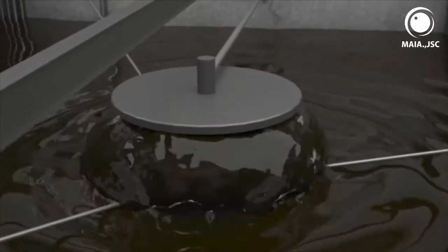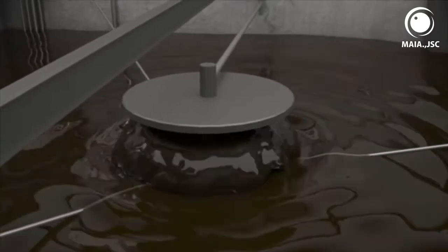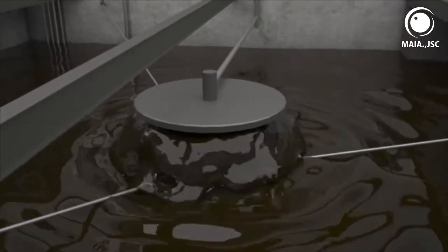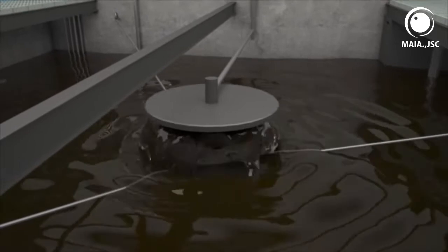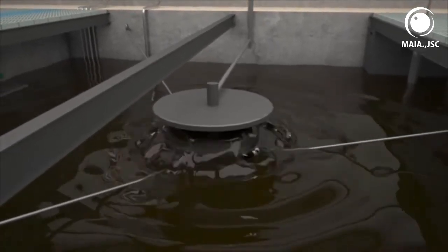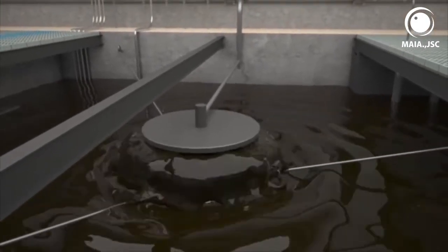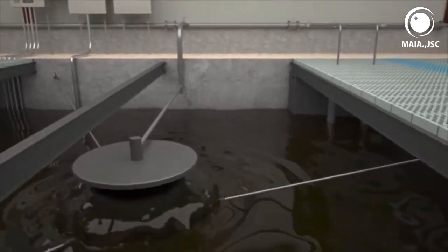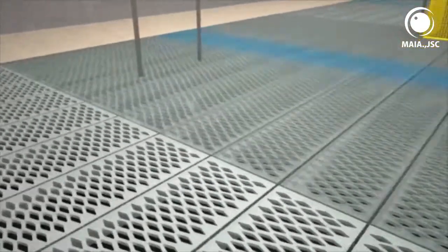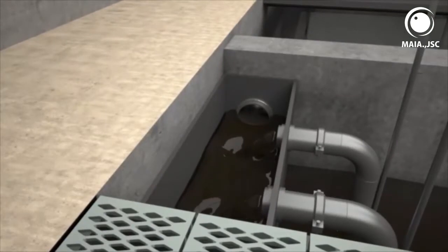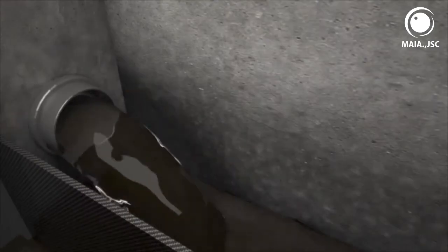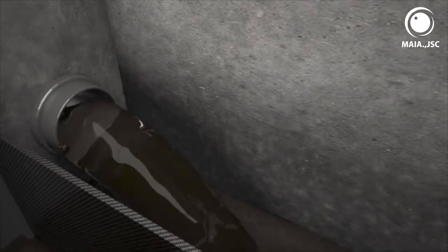This mixing of air and wastewater, along with maintaining the proper room temperature, creates the ideal environment for the aerobic bacteria to digest the biological wastes inside of the wastewater. After approximately 35 hours, the wastewater has been sufficiently treated and is then transferred via airlift pumps into the final settling chamber clarifier tank. The clarifier's job is to separate the aerobic bacteria and leftover solids known as activated sludge from the partially treated wastewater.